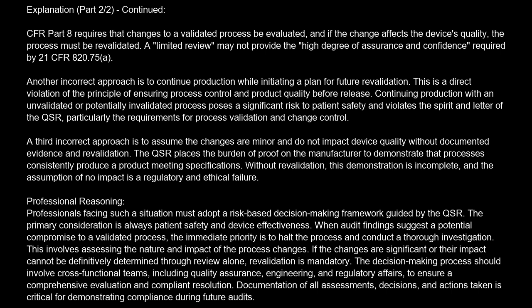A third incorrect approach is to assume the changes are minor and do not impact device quality without documented evidence and revalidation. The QSR places the burden of proof on the manufacturer to demonstrate that processes consistently produce a product meeting specifications. Without revalidation, this demonstration is incomplete, and the assumption of no impact is a regulatory and ethical failure.